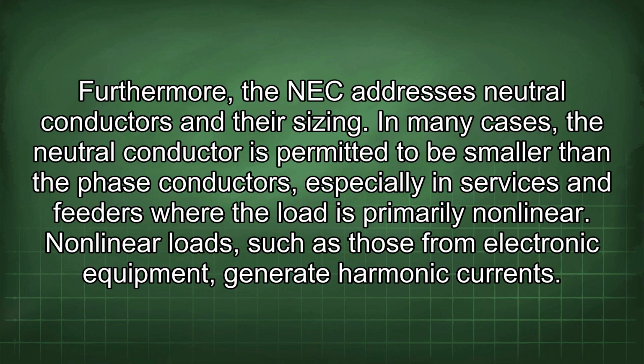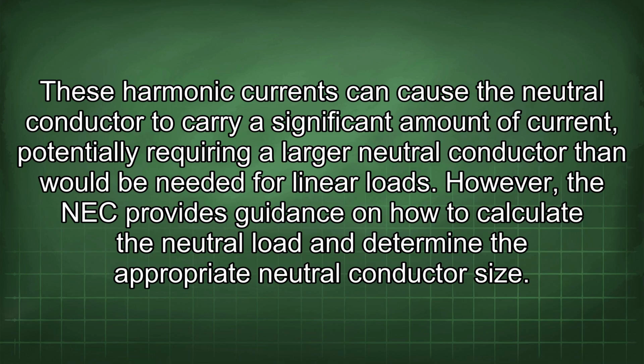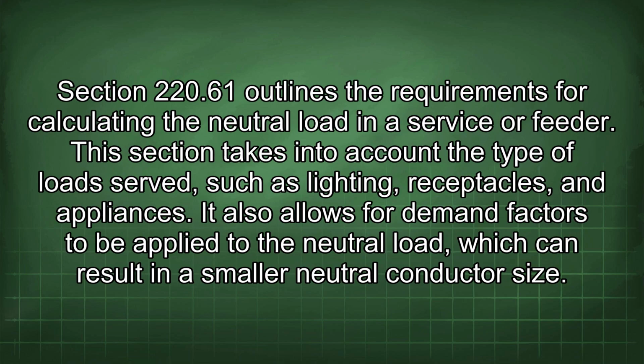Nonlinear loads, such as those from electronic equipment, generate harmonic currents. These harmonic currents can cause the neutral conductor to carry a significant amount of current, potentially requiring a larger neutral conductor than would be needed for linear loads. However, the NEC provides guidance on how to calculate the neutral load and determine the appropriate neutral conductor size. Section 220.61 outlines the requirements for calculating the neutral load in a service or feeder. This section takes into account the type of loads served, such as lighting, receptacles, and appliances.